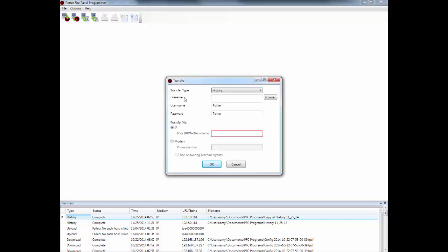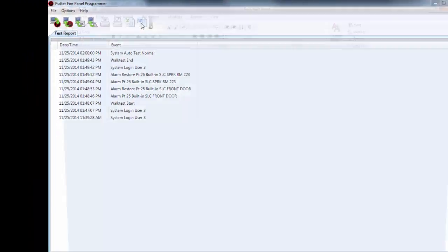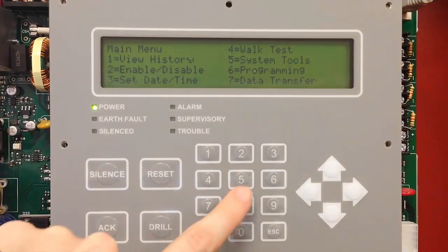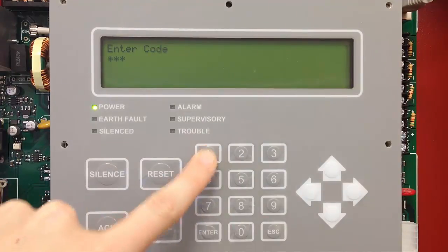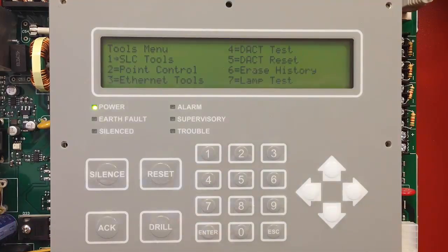Once you've ended the walk test, you can return to the programming software and upload the history to create a test report. When you open up the history, you can see that the walk test started, the points that were tested, walk test ended, and the system is now back to normal. You can export this into Word or Excel to create a test report for your final inspection. Once captured, the last step would be to clear the history, leaving it empty so only events that happen after you leave the site will be listed.